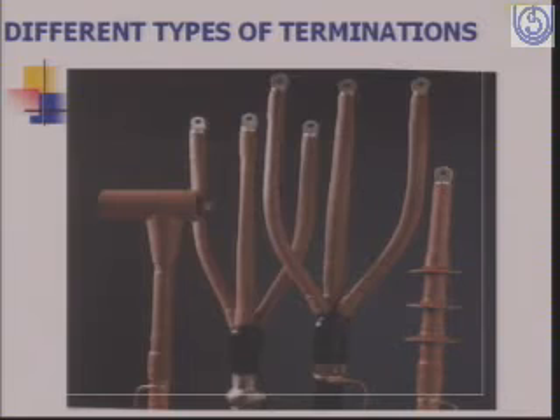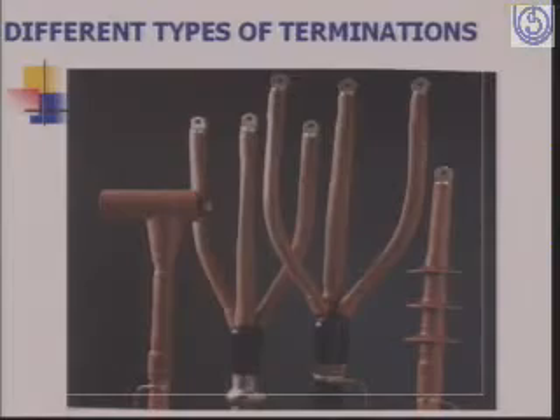When you install underground cables, you have to dig the road, and you should be very sure where the underground cables are placed, because for fault location in a cable, you must know exactly where the cables are placed. But aerial bunched cables can be taken on ordinary poles, they can be taken along the wall of a building. That is the advantage. They can be taken on ordinary communication poles. We can use aerial bunched cables in place of overhead lines. So the 3 types we are using are the overhead line with bare conductor, the overhead aerial bunched cables, and the underground cables.